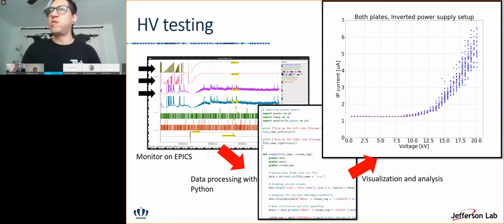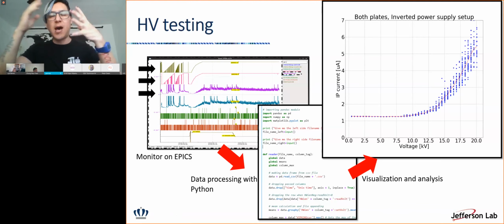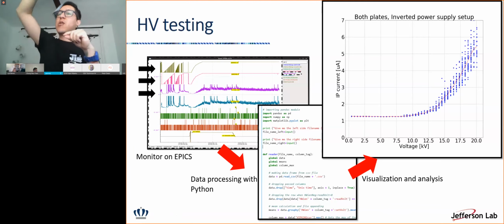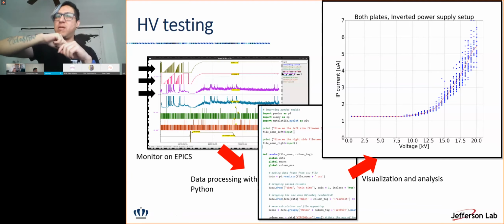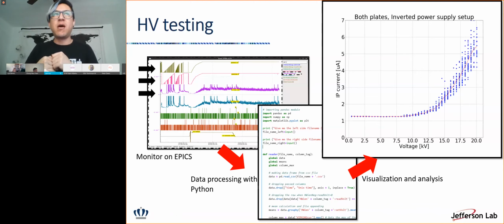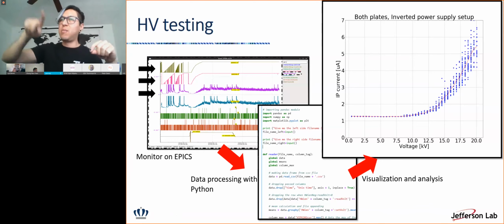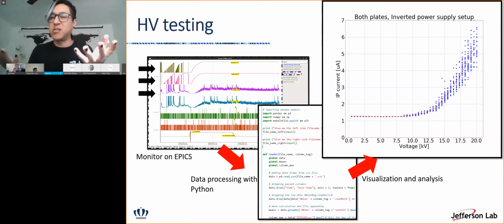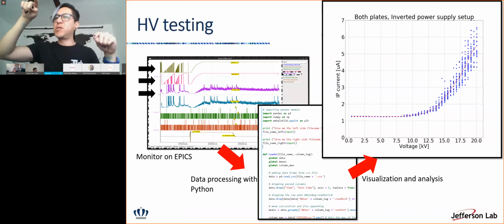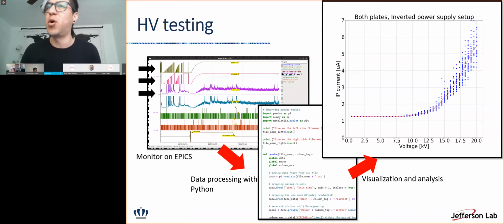Now, how can we use this to say that yes, the device is working properly? One of the things that is very bad from field emission is that sometimes, if the protrusions have specific shapes or behavior, there are huge vacuum bursts that perturb the vacuum enclosure, and they can result in even worse phenomena, like complete device failure by cascading effects and stuff like that. So if we see spikes coming up and down, we can tell, whoa, there's something going on, and that actually happened to us. We need to try to address what is making these vacuum bursts. That's why we also measure the radiation at the same time. So the fact that this plot shows no jumps, that it is just increasing as we increase the voltage, is telling us, okay, the plates are behaving properly.